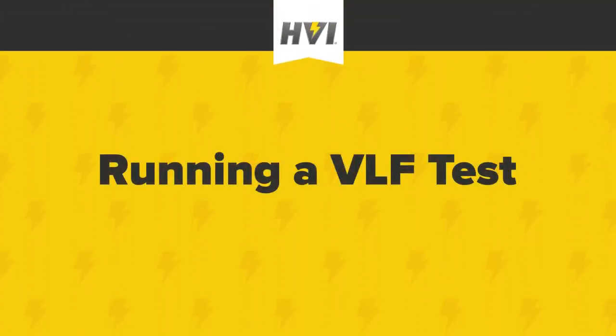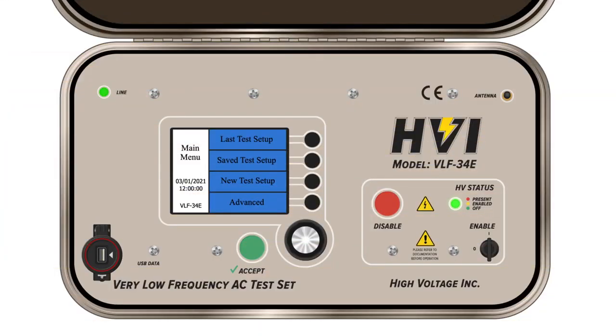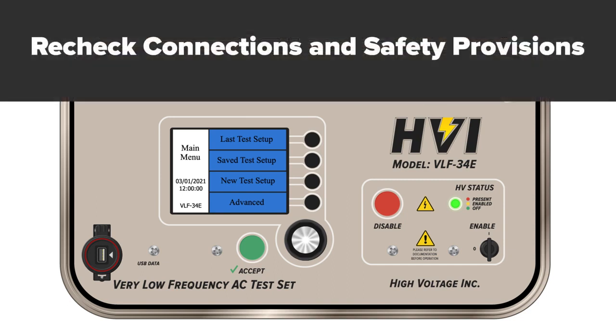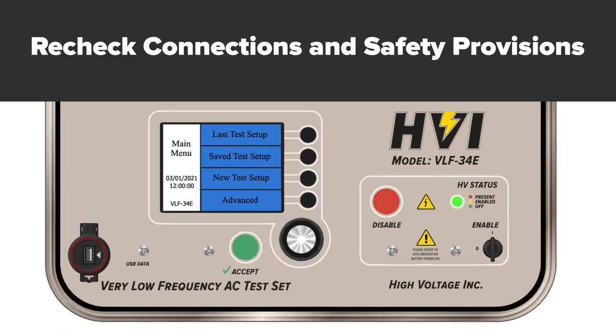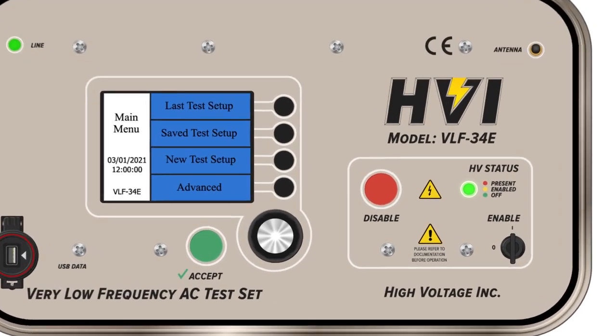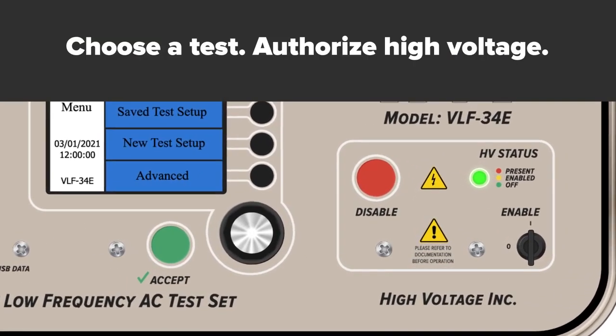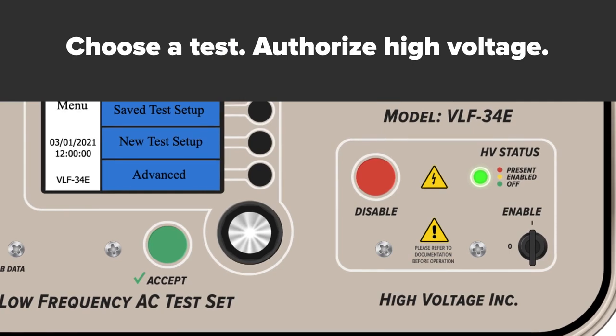Running a VLF test. We'll use the sample test profile we've created for the 15 kV cable maintenance test, using the IEEE 400.2 2013 standard. Recheck all connections and safety provisions, including interlock key. Choose your test and authorize high voltage testing before automatic countdown is over.